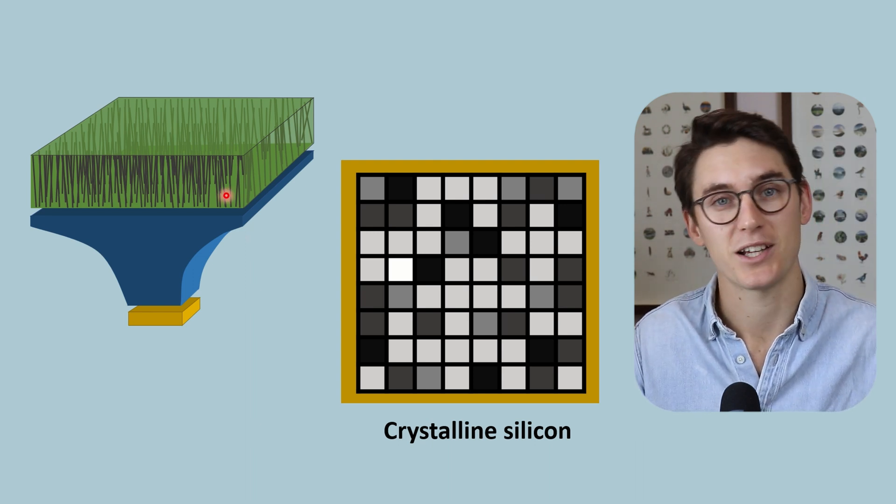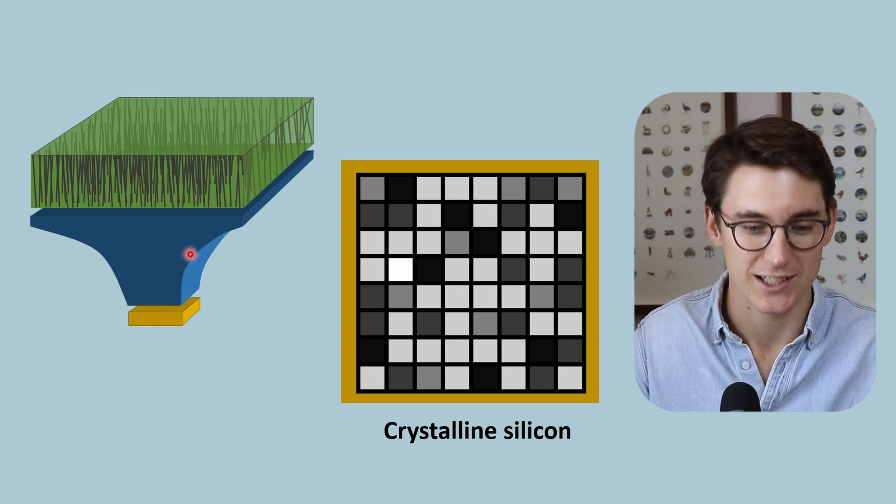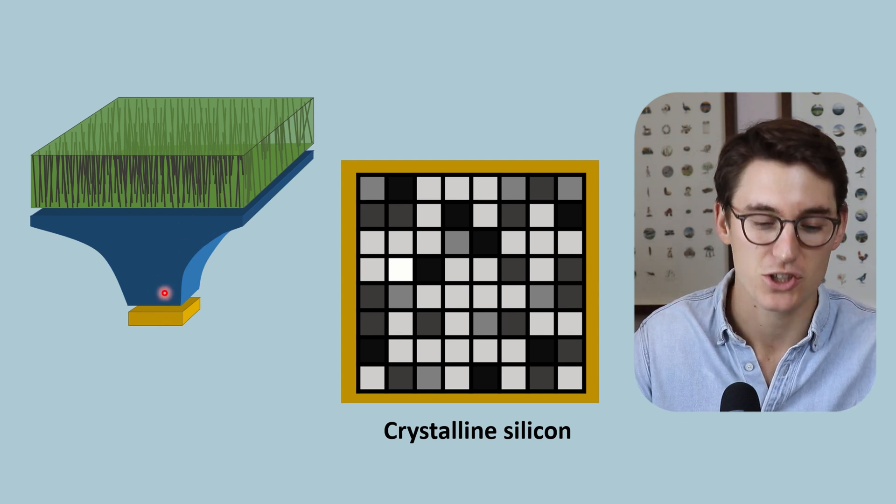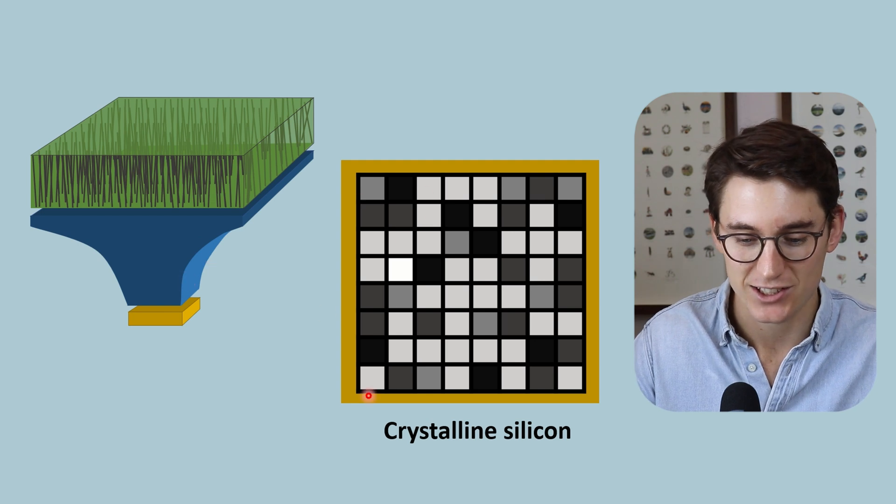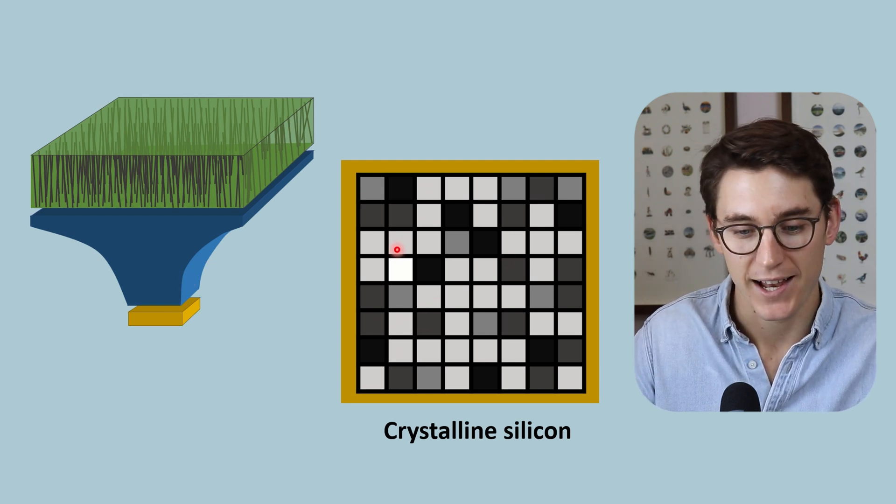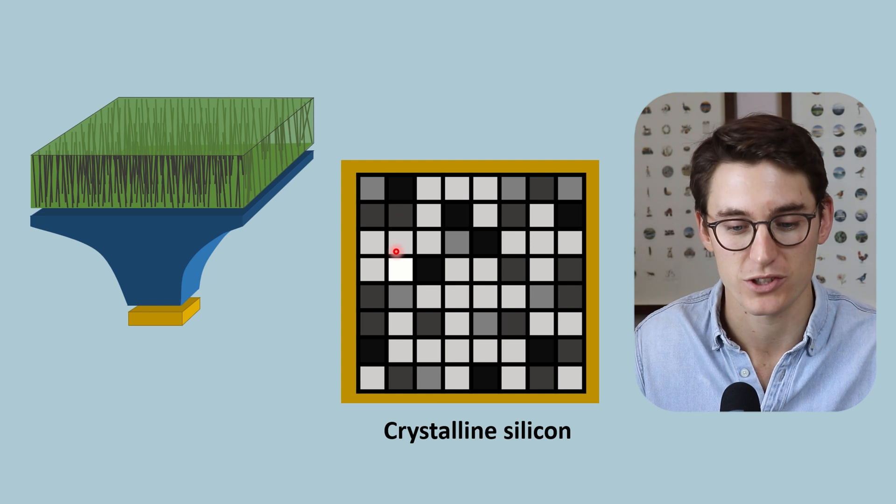Now light is being coupled from this scintillation layer to our CCD chip either by the fiber optic channels or by the lenses that we use. And as that light strikes this silicon layer, electrons are released from the surface of this silicon.